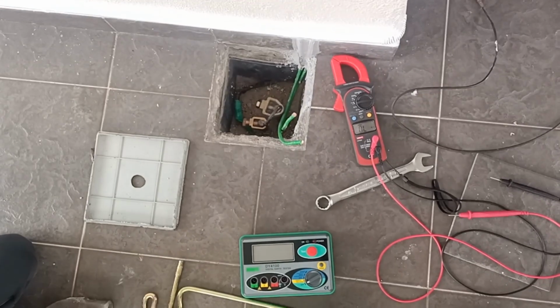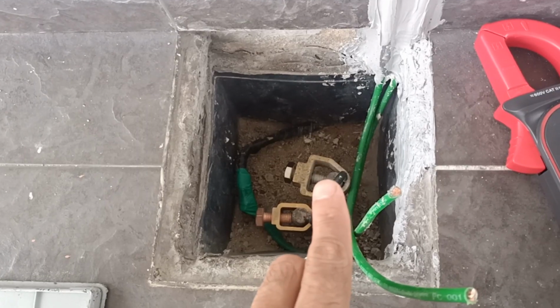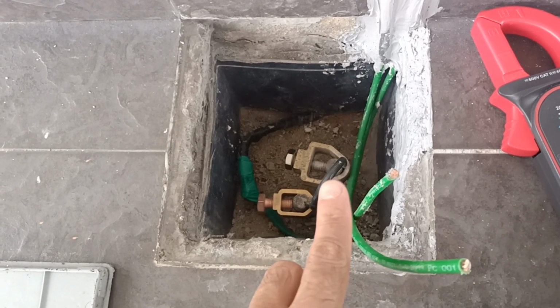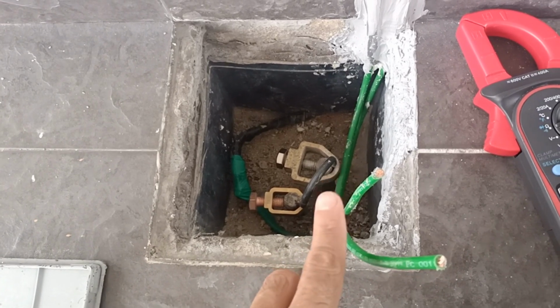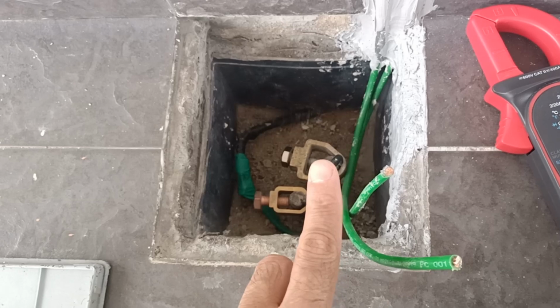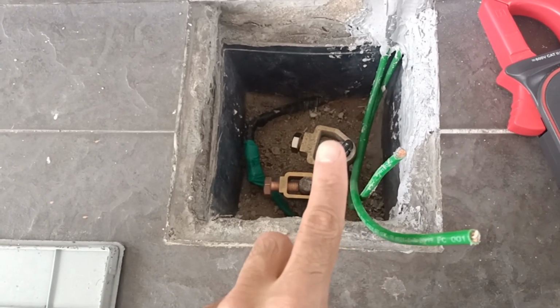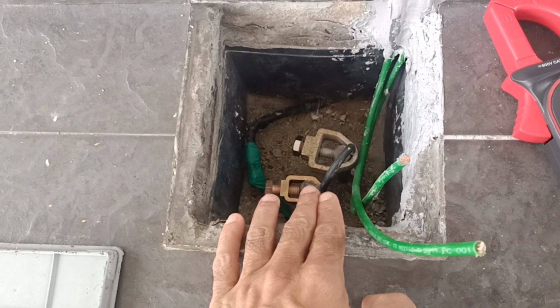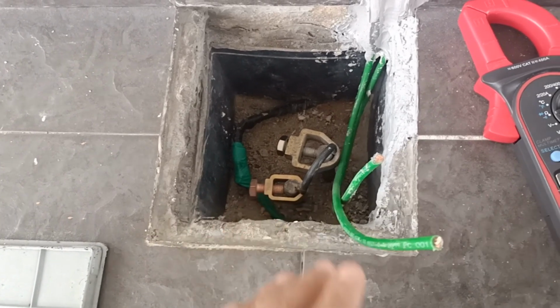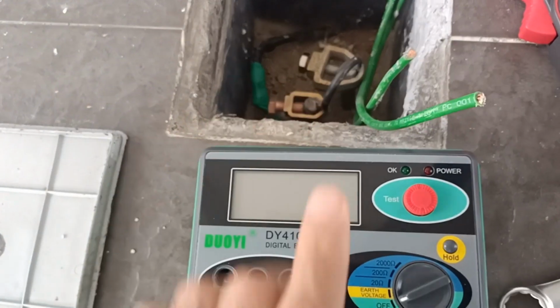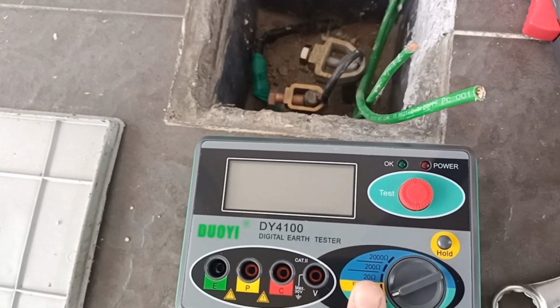We are going to do an earthing test. The resistance of the earth should not be more than 10 ohms, in other words, the lesser the better. So we are going to check the sensitivity of the earth using this digital earth tester.